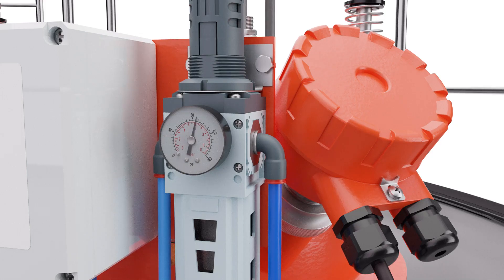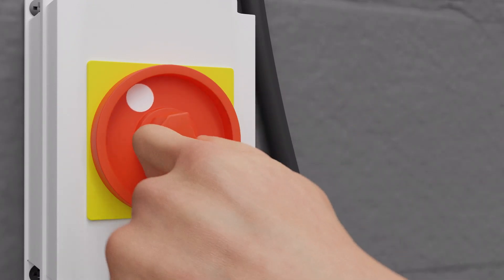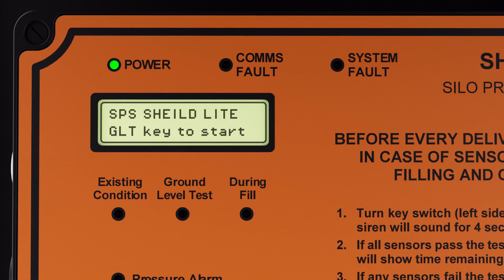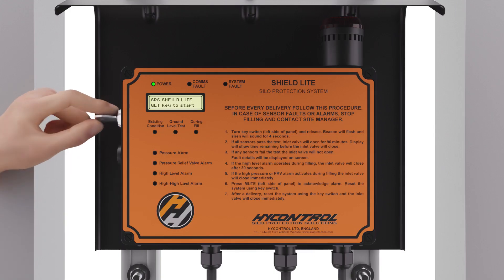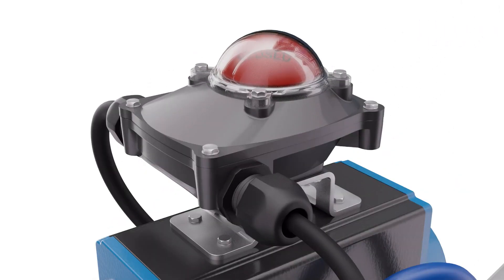Turn on the air supply. The gauge on the PRV should go up to 6 bar or 87 psi. Please note that this is a good time to check for leaks. We are now ready to test that the installation has been successful. Switch on the mains power for the system. If the wiring is correct, you will see the ready screen illuminate on the panel display screen. This should read SPS Shield Lite, GLT to start. To confirm all wiring is correct and the system is operating correctly, run a ground level test by turning the GLT key. The test should pass and open the inlet valve. This confirms that the installation has been successful.